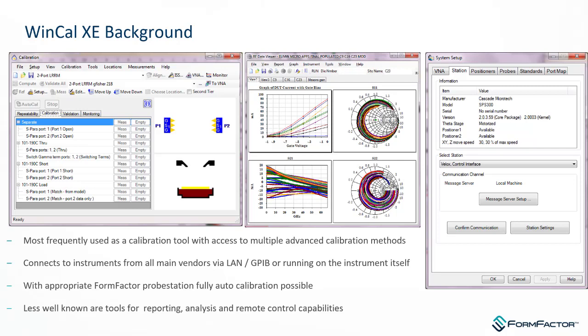Quick overview: if you're not familiar with WinCal, it is FormFactor's — formerly Cascade Microtex — calibration software that remote controls a vector network analyzer and gathers raw measurements, typically of measurement standards: shorts, opens, loads, and throughs. It computes an error set and then loads it back into the vector network analyzer. We're going to go beyond that into things that are not so obvious, learning from example to make your life easier as a microwave engineer.